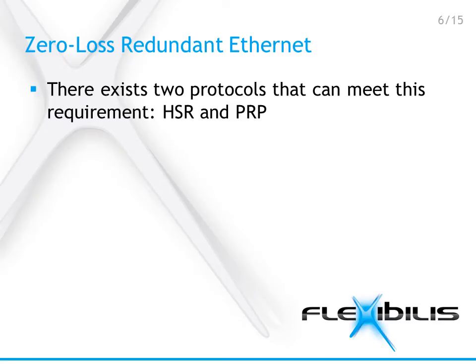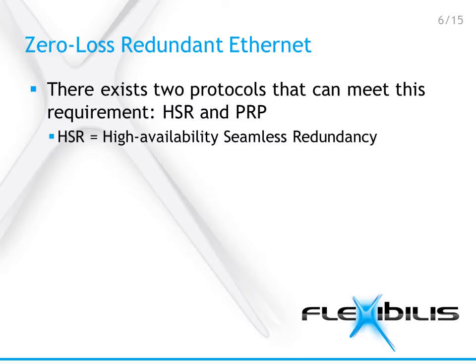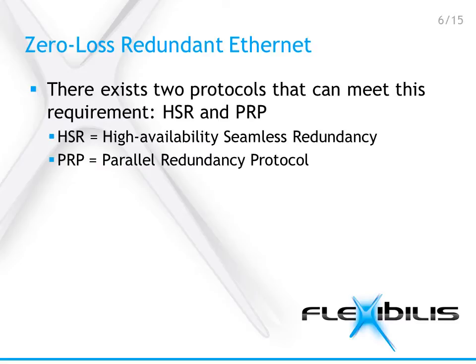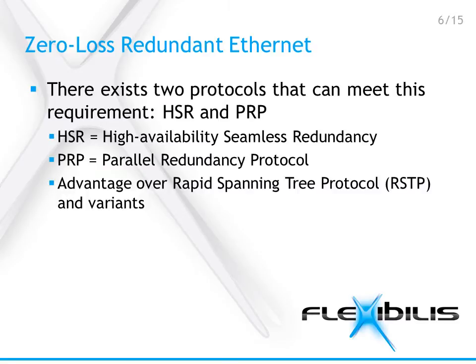There exist two protocols that can meet the requirement for zero-loss redundancy: HSR and PRP. HSR means High Availability Seamless Redundancy, and PRP is Parallel Redundancy Protocol. The difference between these two is that HSR has double data and PRP doubles everything. The advantage over Rapid Spanning Tree Protocol, RSTP for short, is that HSR and PRP have zero-time recovery in case of failure.